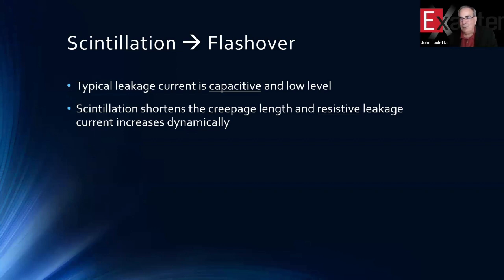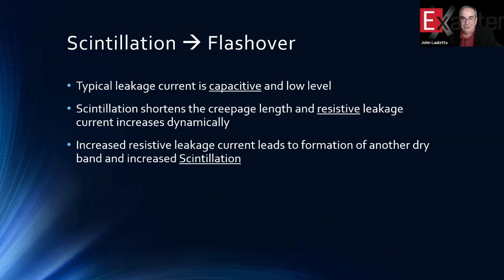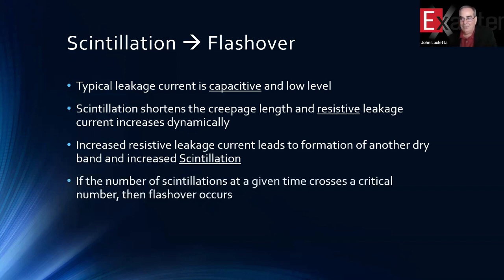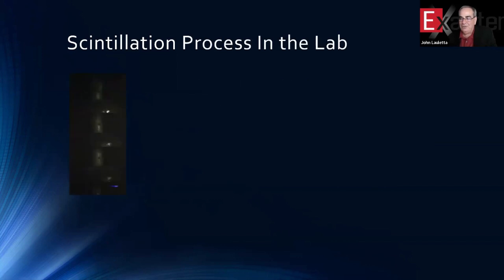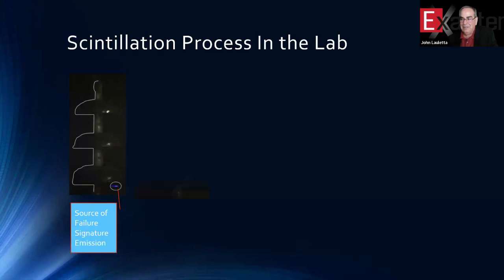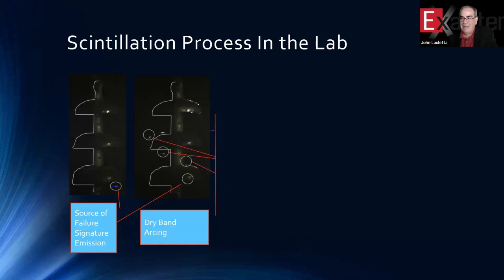We've talked about the currents, how they move from capacitive to resistive, how they increase during this period of scintillation. And if the number of scintillations on an insulator crosses a critical number, a flashover is going to occur. You can't see this very well, but here I outlined an insulator in a laboratory setting. It's in the dark, so we can see the scintillation actually occurring. And there's a source of the failure signature emission, that little blue light underneath one of the dishes of the insulator itself. The dry bands themselves, we add to the insulator to demonstrate the problem of collecting dry bands and the impact that has on the operation of the insulator.